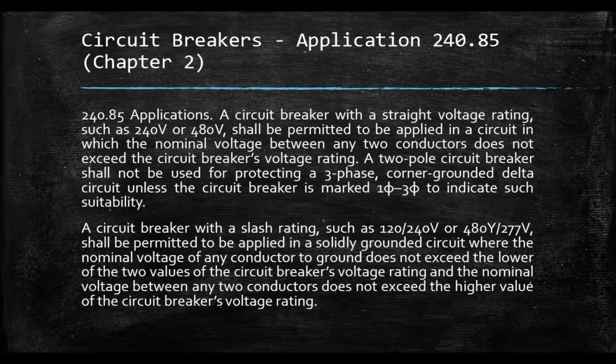A circuit breaker with a slash rating such as 120/240 volts or 480Y/277 volts shall be permitted to be applied in a solidly grounded circuit where the nominal voltage of any conductor to ground does not exceed the lower of the two values of the circuit breaker's voltage rating, and the nominal voltage between any two conductors does not exceed the higher value of the circuit breaker's voltage rating.